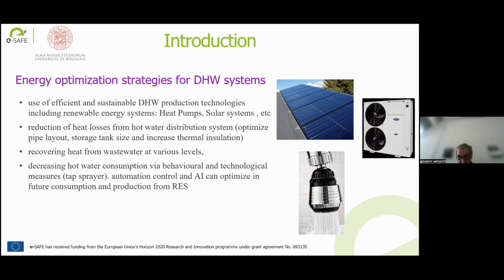First, by reducing the time of using hot water or the shower, reducing the consumption, let's say. Second, an important aspect is to decrease the draw-off temperature of domestic hot water. Some users use water at up to 50 degrees. Normally, it's possible to use it at 35, 40 degrees.